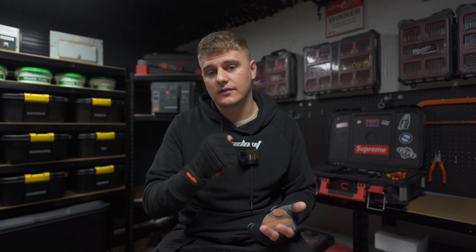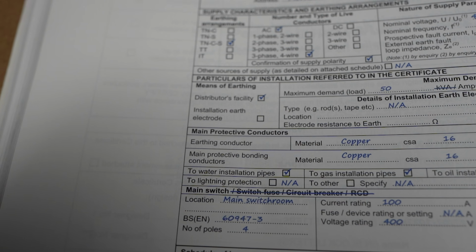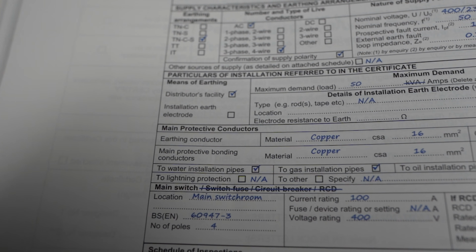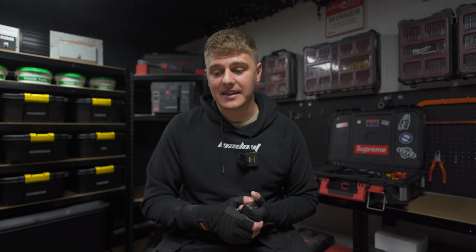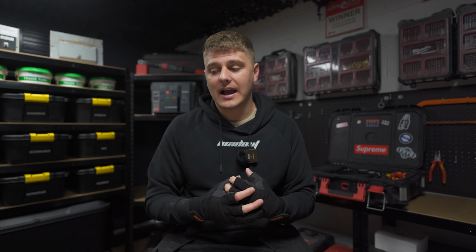So this second test just verifies that, and you're looking for around the same result immediately after the connection point. If both values are below 0.05, then the test is considered satisfactory and it's complete. So that's the test done. Pretty easy, right? Like I said, it's super heavy on the theory and the information and the science behind why we do it. However, when it comes to actually testing them, it's super easy.